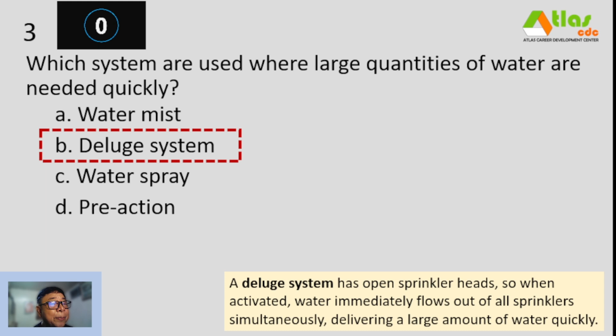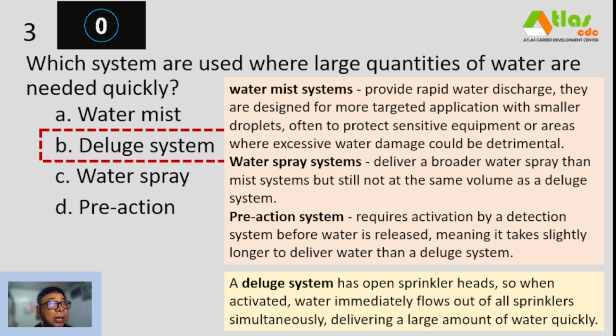Water mist systems provide rapid water discharge. They are designed for more targeted application with smaller droplets, often to protect sensitive equipment or areas where excessive water damage could be detrimental. Water spray systems deliver a broader water spray than mist systems, but still not at the same volume as a deluge system. Pre-action system requires activation by a detection system before water is released, meaning it takes slightly longer to deliver water than a deluge system.